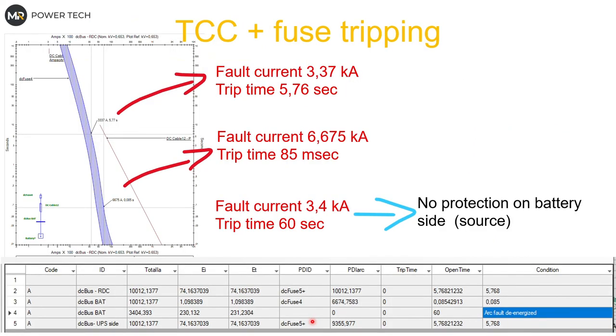Looking at the time-current curves: I had to recreate the AC fuse behavior on DC just to show the difference. The problem was that tripping each battery for an external fault was relatively slow — approximately 5.76 to 6 seconds — because it saw approximately 3,000 amps. Two batteries feeding a third would trip relatively fast in about 85 milliseconds. But the battery itself has no additional protection, so it stays energized with full current until everything burns down.